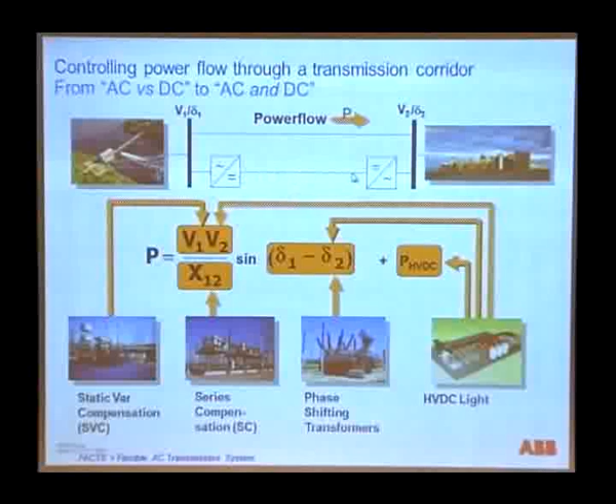At the same time, we've got these new components that we are closing very different loops with today, and that's static VAR compensation—power electronics working on controlling reactive power and voltage levels. And we've got voltage source converter, high voltage direct current, which is basically a very controlled pipeline in parallel to the existing one, giving us a great way of controlling the flow of power that just wasn't there.